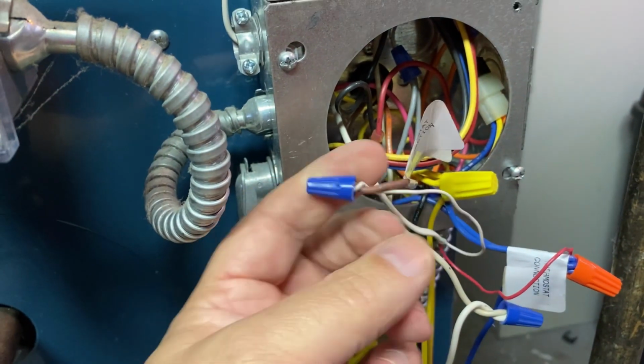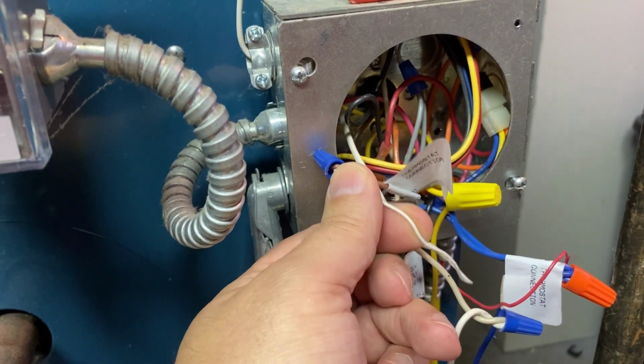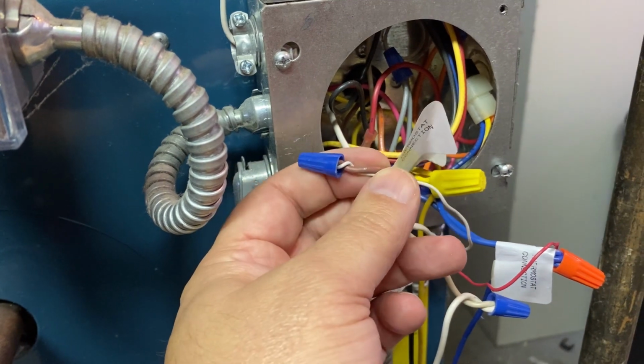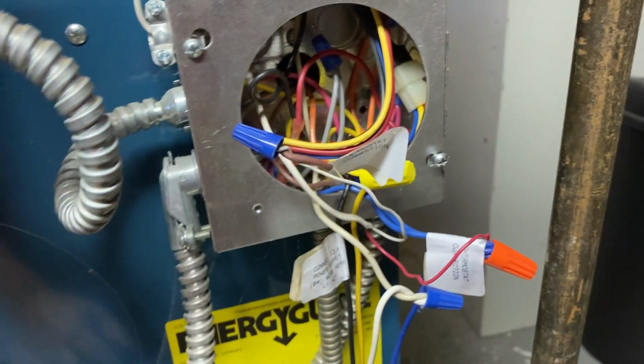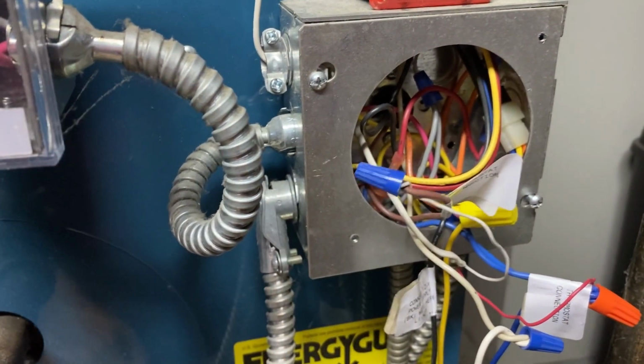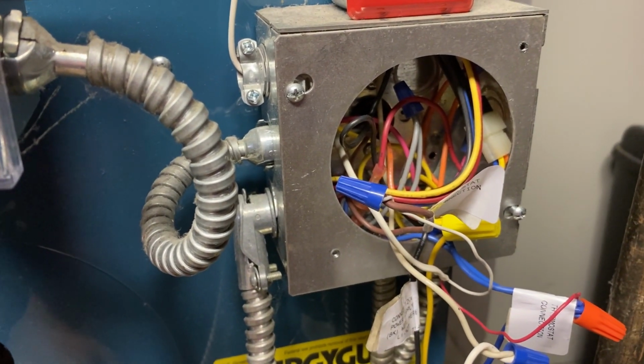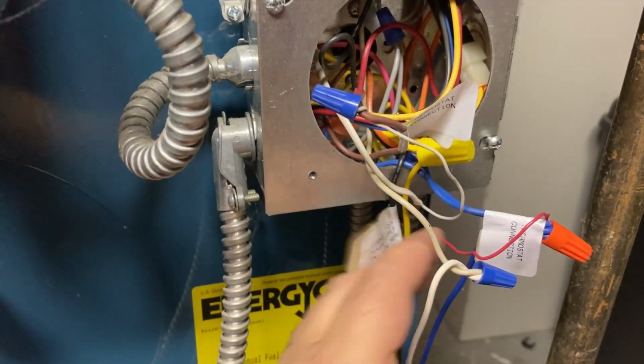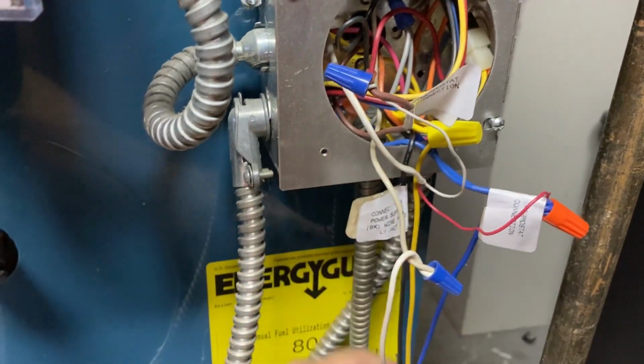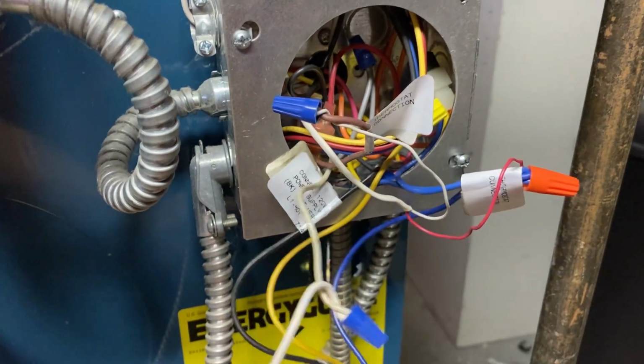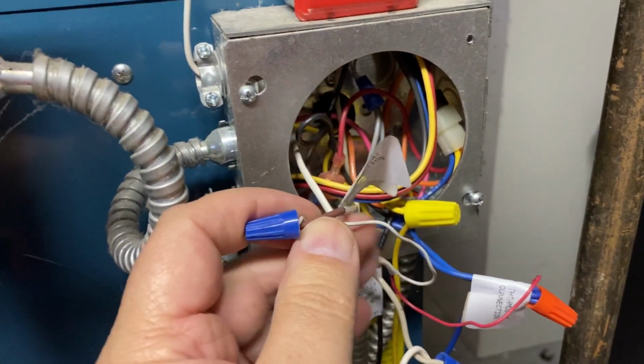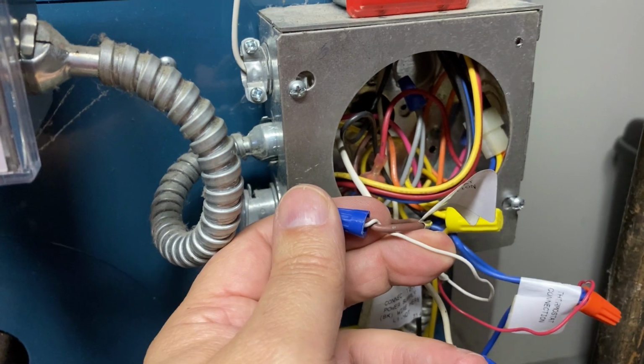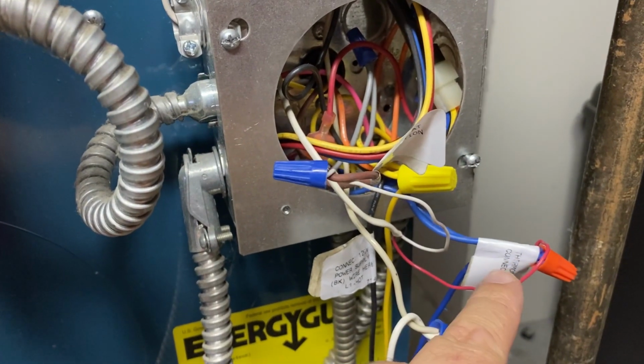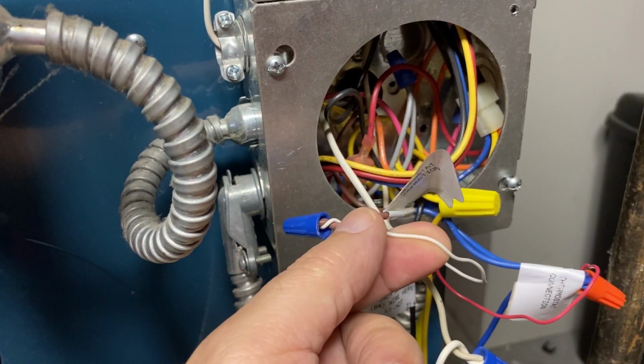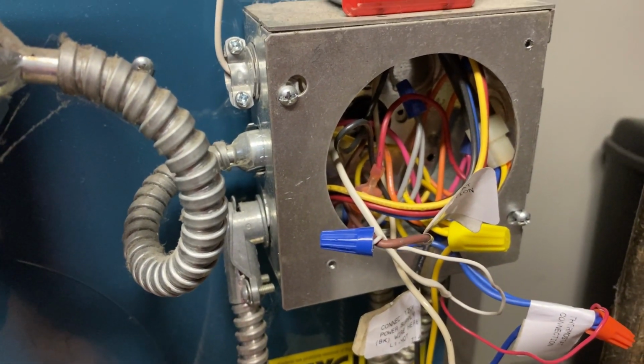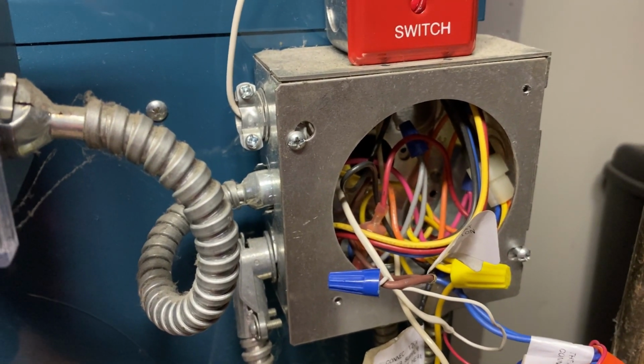And this is the switched wire. So this is the return. This white wire is the return from the thermostat. So that goes into the other thermostat connection. And this brown wire basically tells the system to turn on once the thermostat requires it. So that's what it is. So the red wire is the 24 volt feed from the transformer. And the white wire is going to be the return. So I will make this the R upstairs, and I will make this the W upstairs. Kind of easy. Now I'll put this plate back on, and we'll go back upstairs.